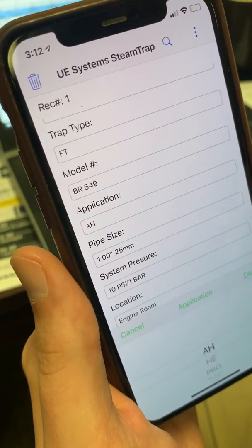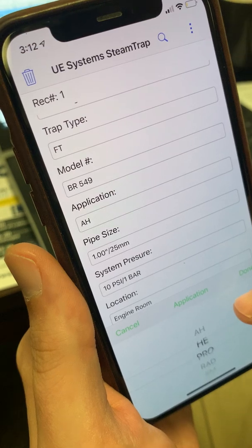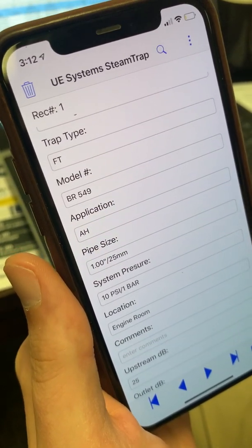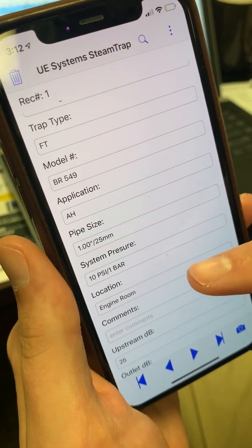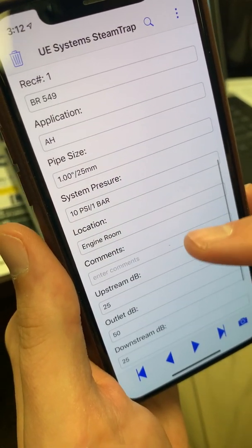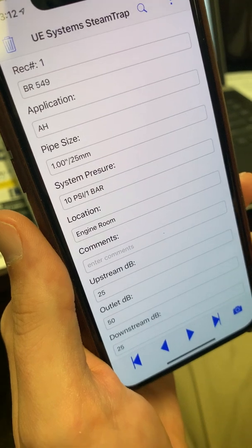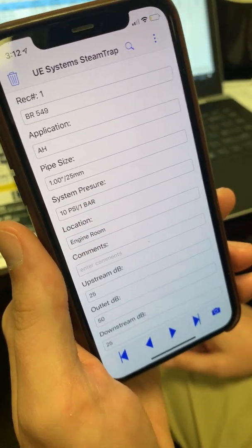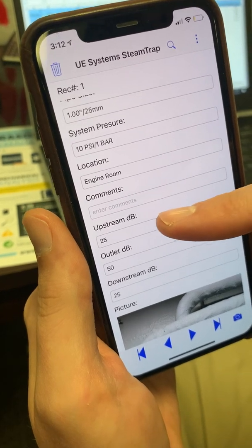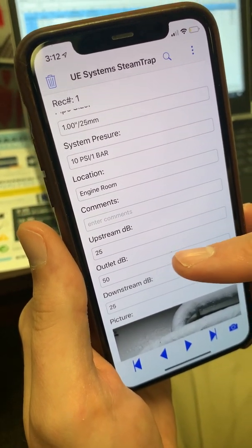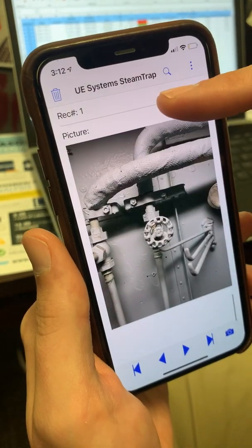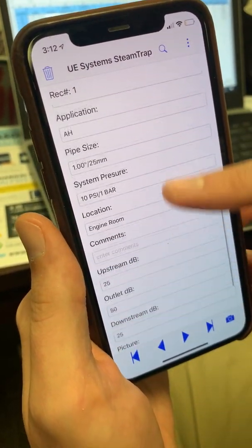As far as Application, you can select air handler, heat exchanger, and similar options. Right here you can adjust your system pressure, type in comments about where you actually are — your location and any other notes, such as where the steam trap is located to help you identify it in the field. We also have spots for the upstream dB, outlet dB, and downstream dB. You can also take a picture of the trap.